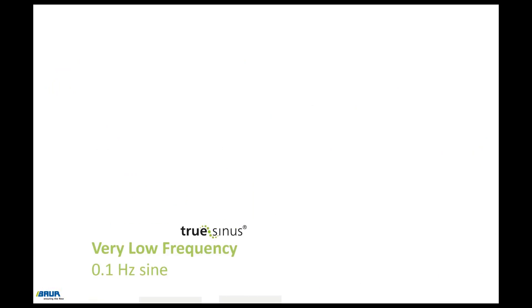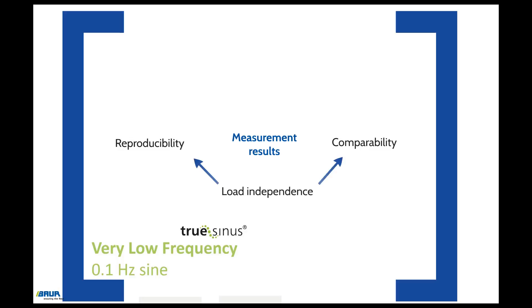Despite the advantages and disadvantages of each of the different testing and diagnostic methods — such as 50 Hz sine, 0.1 Hz sine, DAC, and 0.1 Hz cosine square wave — the 0.1 Hz voltage shape has the decisive advantage of reproducible and comparable measurement results. This is due to its load independence, which can only be achieved by the true sinusoidal 0.1 Hz voltage.